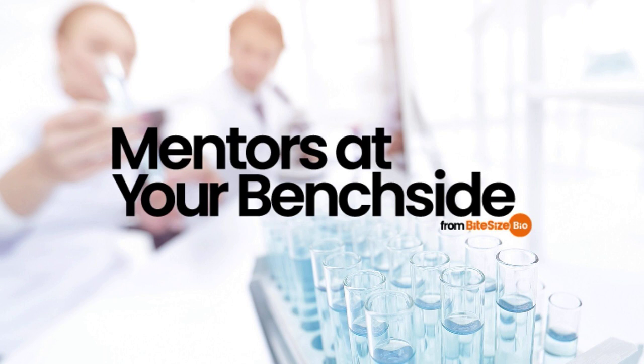Now we know how pH meters work, let's learn how to look after a pH meter in 4 steps. Number 1. Take care of the pH meter probe. The pH meter probe should never dry out. Should the probe dry out, it will break or at least become unreliable. I once had a run of unsuccessful yeast transformations because the pH meter was wrong by 0.2. Don't let this travesty happen to you.